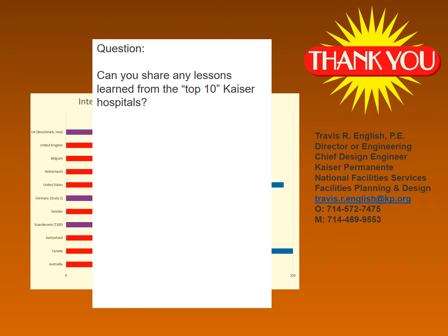A little bit. A lot of it has to do with the site operators, so just capturing opportunities is important. In terms of systems, cogeneration systems are heavier in the top 10 than in the bottom 10. The system I can tell you is a dead bust is thermal fluid heaters. We have about 4 sites with thermal fluid heaters, and they are all soundly in the bottom 10 — those things are burning energy like it was still in style.